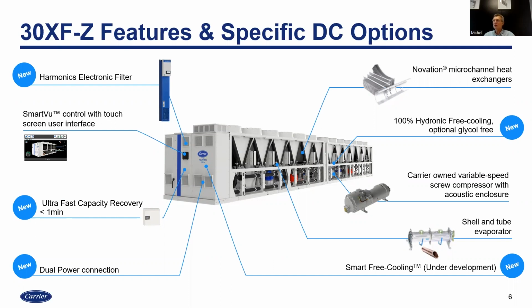At 100% load that's 100% of flow, but if you go down to 25 or 30% load, your water flow should also be 25 or 30% of full load to maintain the same temperature differential. This is a challenge for heat exchanger design, because when you reduce water flow too much, you can enter laminar flow, and heat transfer is reduced drastically.